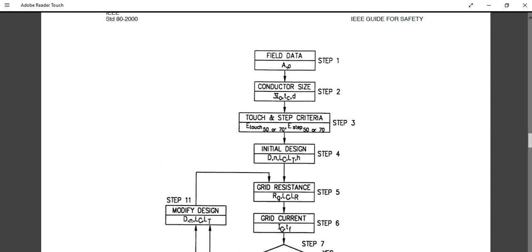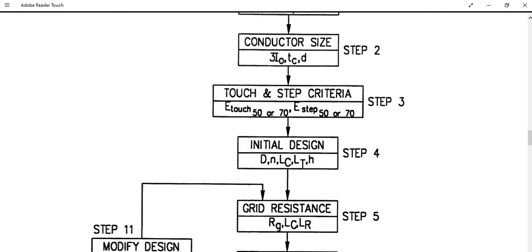Step 3 is the calculation of touch and step criteria. Using the formula provided in IEEE 80 standard, you calculate the tolerable touch potential (E-touch) and step potential (E-step). Step 4 involves the preliminary selection of the ground grid — the initial design considering main ground grid material and ground rods.